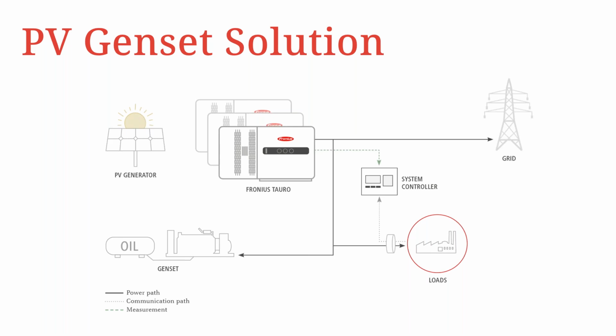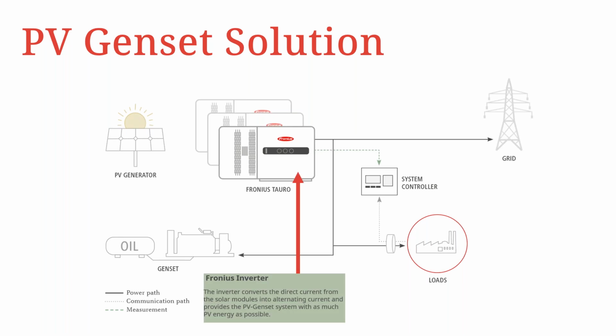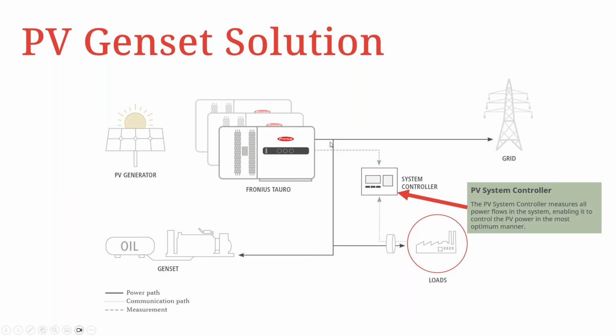So this is like a single line diagram of the PV-Genset solution. To start off, we have the Fronius inverter, which converts the DC to AC, and then supplies it to the AC line, the common AC bus bar. Then we have the PV system controller, like I earlier defined, as the heart or the brain of the system, which measures the power flow of the entire system, and then determines when to throttle up or throttle down the PV supply into the system.